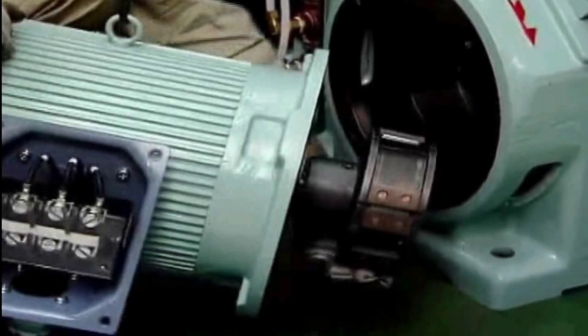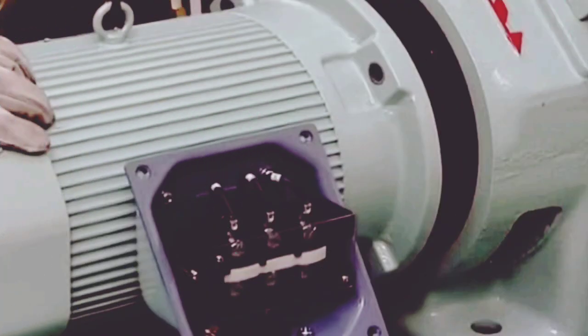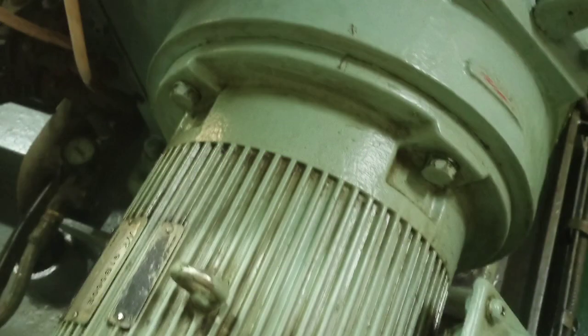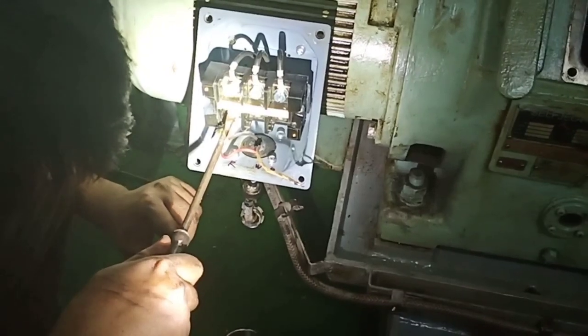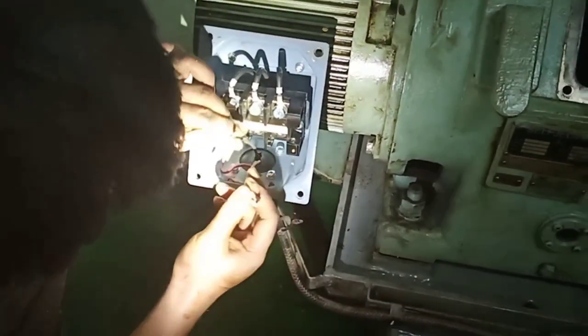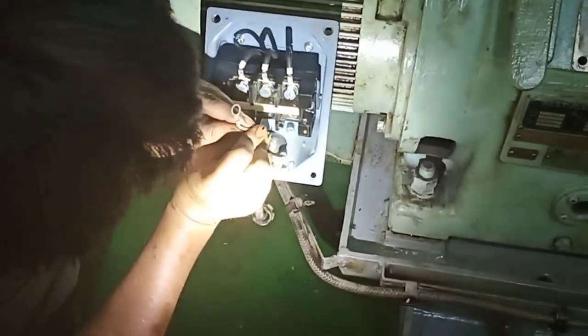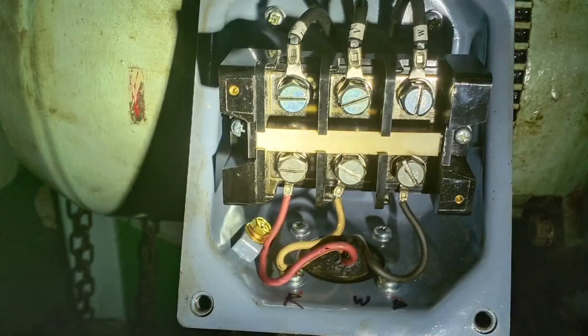Lift the motor with chain block. Fasten the four bolts and tighten the bolts to mount the motor. Connect the motor wiring accordingly. Make sure that it is properly connected according to markings or numbers to prevent the motor running in reverse.